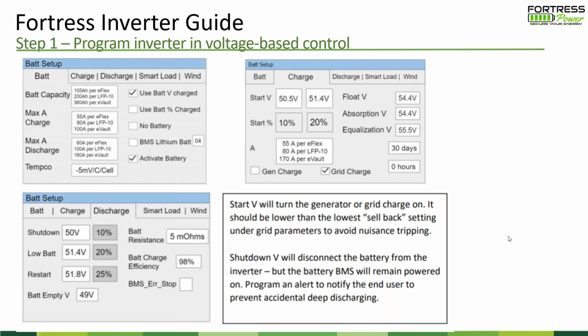So step one is to program the voltage-based controls. One key is to disable equalization, so make sure that's turned off. Not all of these program settings are set in stone, such as the low battery alarm, the shutdown voltage, or the restart voltage.